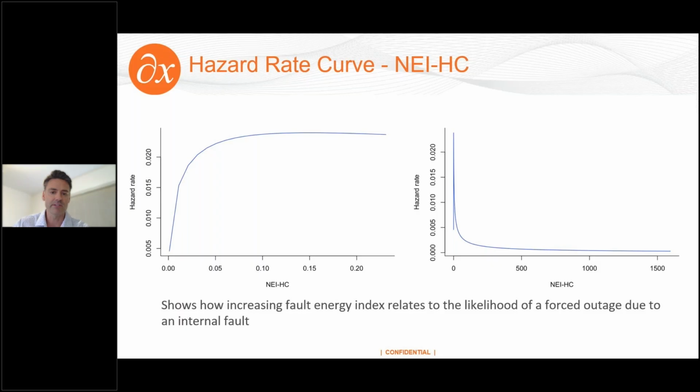risk of near-term failure. So when a transformer starts to produce gas, this indicates that something is wrong, and in some cases that problem is bad enough to take out the transformer quickly. So the real lesson here is that in the early stages of gassing, there's an opportunity to investigate or intervene and possibly save the transformer, and early detection and response is critical.